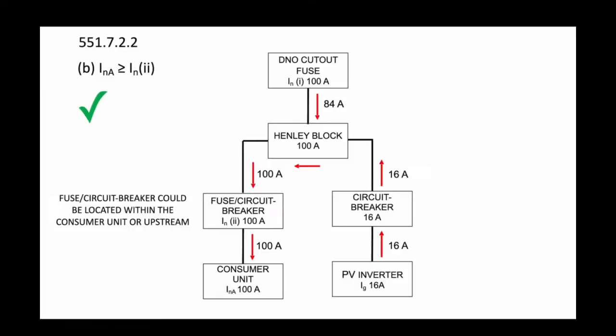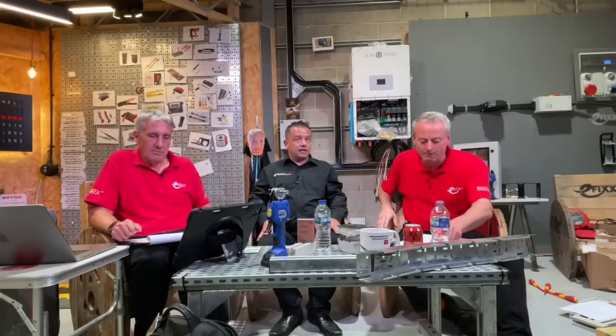Now, I appreciate that when you've got socket outlets, that becomes very difficult because you can't control what's going to be plugged in. But the fuse is there for short circuit protection. It's there for fault protection, in particular the DNO fuse. They're not useful at all for overload protection. That's what people quite rightly would say. Well, apart from the Henley block one, which you got out of, but that's what people would jump in on.